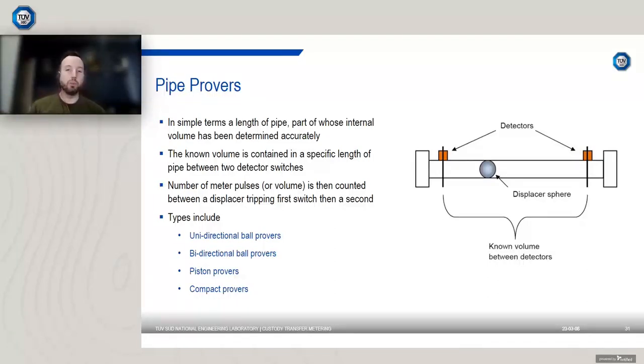I'm going to talk about pipe provers because these are quite a common type of prover used in custody transfer. So what is it? Well, in simple terms, it's a length of pipe, part of whose internal volume has been determined accurately. You've got the known volume, contained between detector switches. There's some form of displacer in the pipe; it might be a sphere, it might be a piston. As flow moves through the pipe prover, the displacer triggers the first detector switch. That's when you start counting the pulses from your flow measurement device. It triggers the second detector switch. That's when you stop the pulse count. So you get a total number of pulses. You know the calibrated volume. You can work out a K factor or you can determine a meter factor.